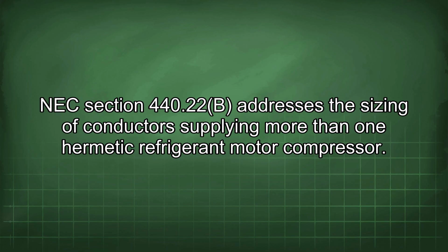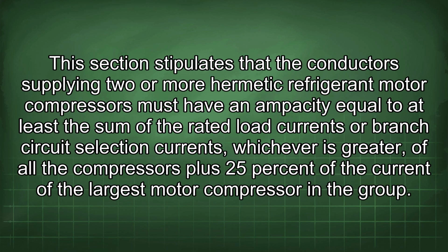NEC Section 440.22(B) addresses the sizing of conductors supplying more than one hermetic refrigerant motor compressor. This section stipulates that the conductors supplying two or more hermetic refrigerant motor compressors must have an ampacity equal to at least the sum of the rated load currents or branch circuit selection currents, whichever is greater, of all the compressors plus 25% of the current of the largest motor compressor in the group.